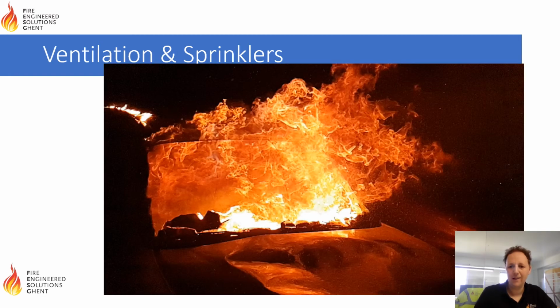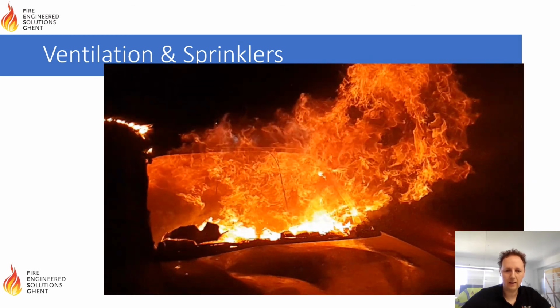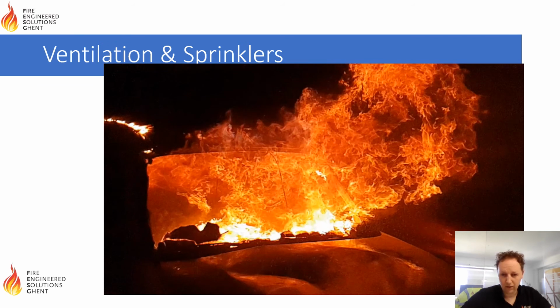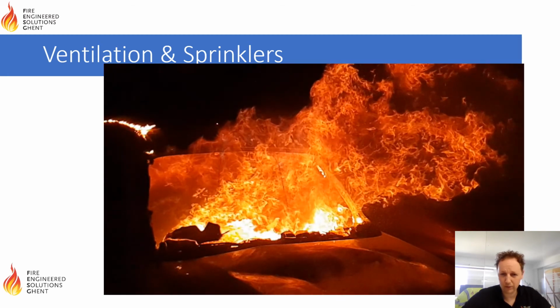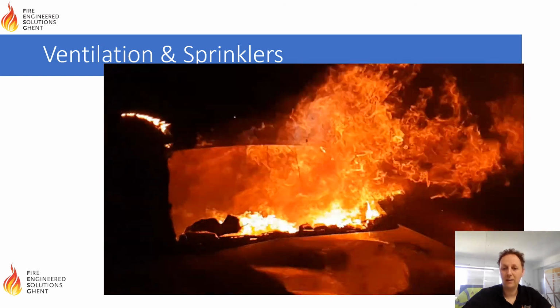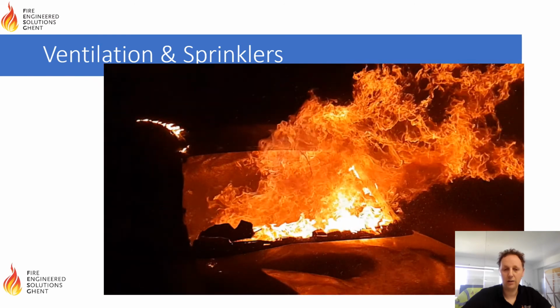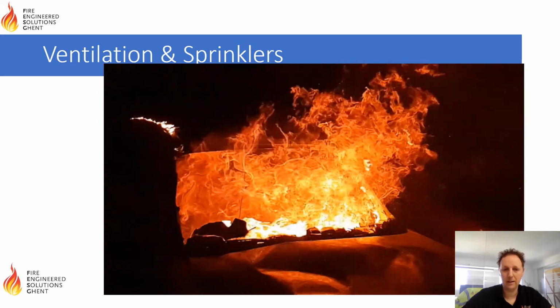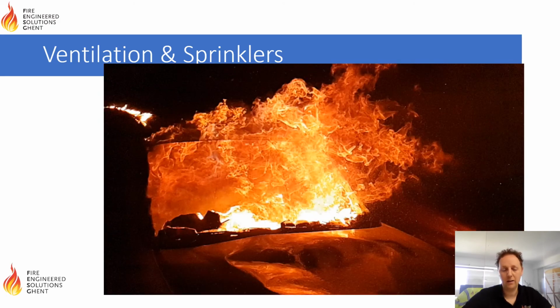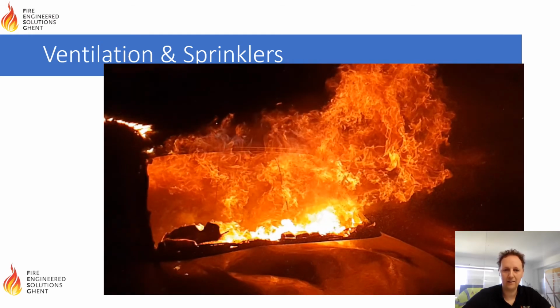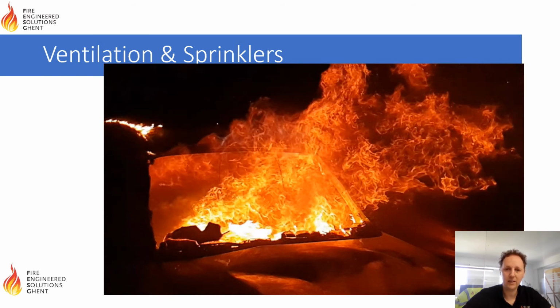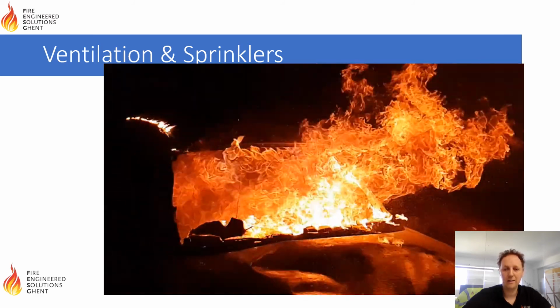Now let's compare this. Okay, interesting to compare now to a second test where we had combined longitudinal ventilation around 1.5 meters per second and the sprinkler according to the standard ordinary hazard 2. And let's have a look at the interaction. So what we see here is that the sprinkler droplets are visible on the downstream. So you can see the droplets coming down, but you also see that they don't have an impact on the tilted flame. Basically, the ventilation makes sure that the maximum heat release rate in the burning car can still be obtained, and it's a totally different situation, ventilation and sprinklers compared to sprinklers alone. So basically, you have an advantage that you have a smoke-free access, but the disadvantage is that you have much higher heat release rate, higher temperatures, and that the efficiency of your sprinkler is much lower.